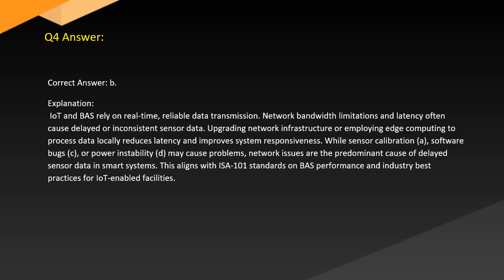Answer. Correct answer: B. Explanation. IoT and BAS rely on real-time, reliable data transmission. Network bandwidth limitations and latency often cause delayed or inconsistent sensor data. Upgrading network infrastructure or employing edge computing to process data locally reduces latency and improves system responsiveness, while sensor calibration (A), software bugs (C), or power instability (D) may cause problems. Network issues are the predominant cause of delayed sensor data in smart systems. This aligns with ISA 101 standards on BAS performance and industry best practices for IoT-enabled facilities.